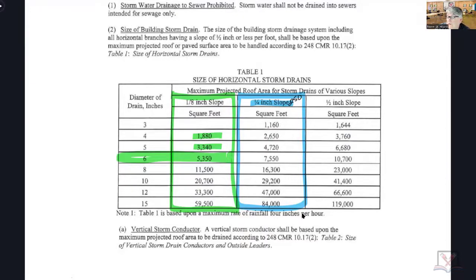How can I remember that? Quarter-inch pitch is 0.25, even though that has nothing to do with the constant. It has nothing to do with it. It's just 250 square feet of roof area will drain through a one-inch pipe in one hour. This one was 200. Half-inch, 300.